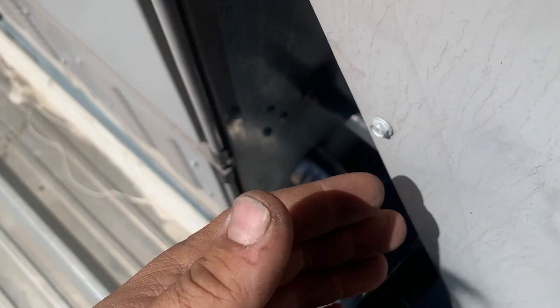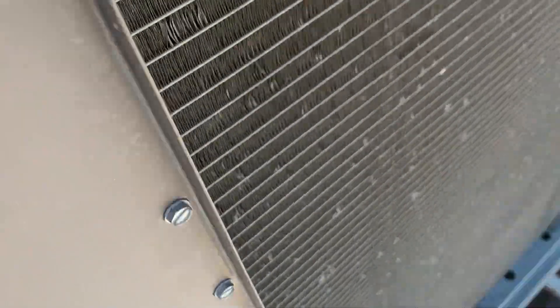I don't know if you can tell, but there's a lot of motion in this motor — almost like it's hula hooping. It's creating lots of vibration. Our last leak on the other unit was right up there. However, we've got this really big vibration, so we should probably start with a search right back here.